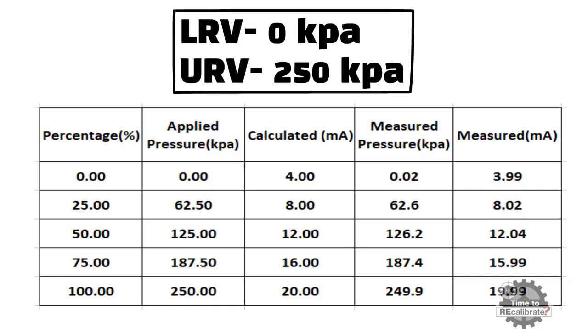Now, repeat the same steps for 50% of input, 75% of input and 100% of input. For example, apply approximately 125 kPa of pressure to transmitter, and note down measured pressure value from transmitter display. Measured pressure value should be nearest to 125 kPa. At the same time, note down the value of milliampere from digital multimeter. Measured milliampere value should be nearest to 12 milliampere. At the end, apply 250 kPa of pressure to transmitter, and note down measured pressure value from transmitter display. Measured pressure value should be nearest to 250 kPa. Measured milliampere value should be nearest to 20 milliampere. 5-point verification is done.